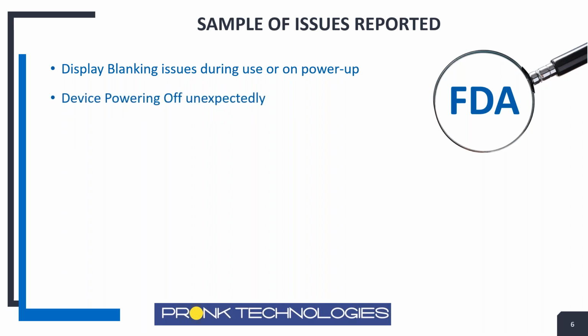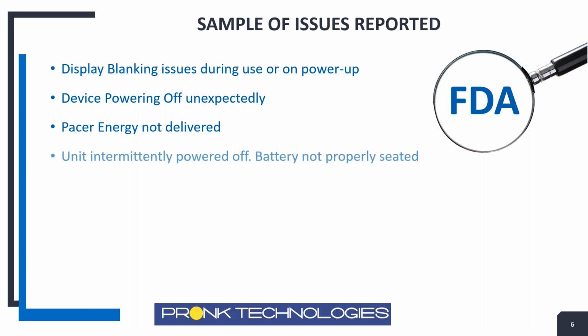The device was powering off unexpectedly. So someone's trying to use the defibrillator and it just powers off. You have pacer energy not being delivered when they expected it. So they programmed the defibrillator, but the pacer energy was not delivered. The unit intermittently would power off. This was one specific case we noticed.